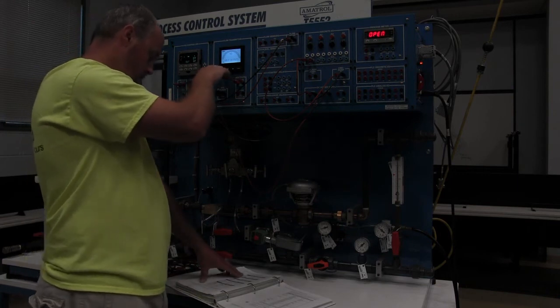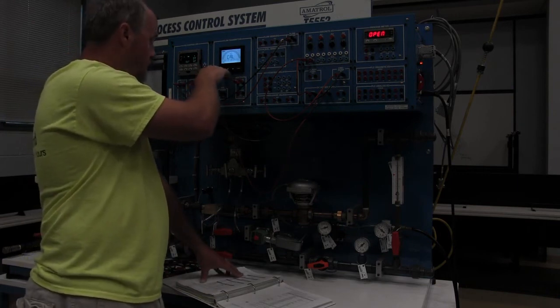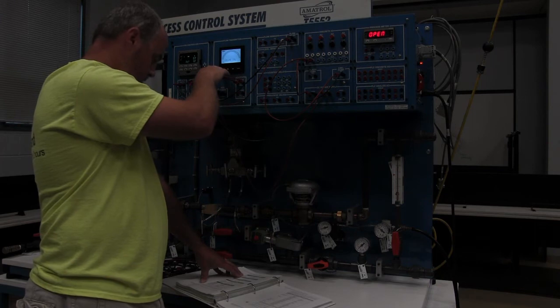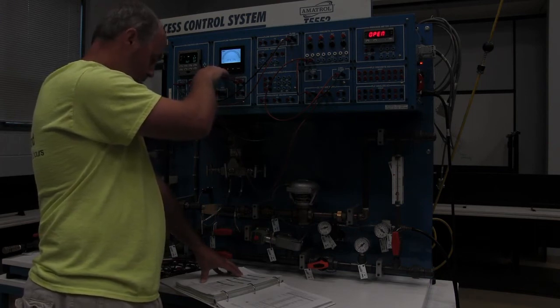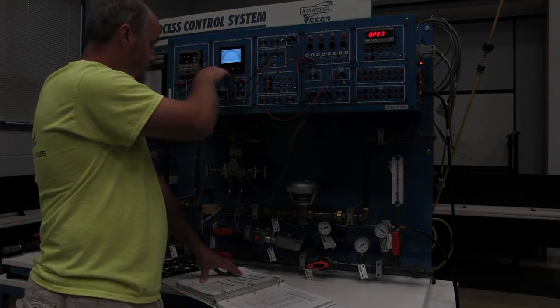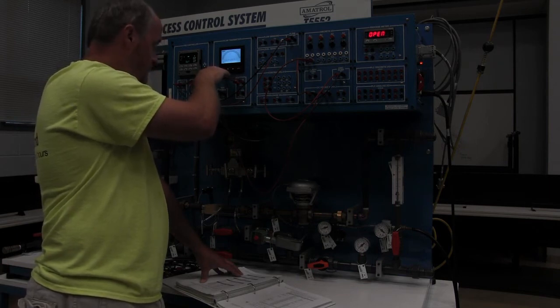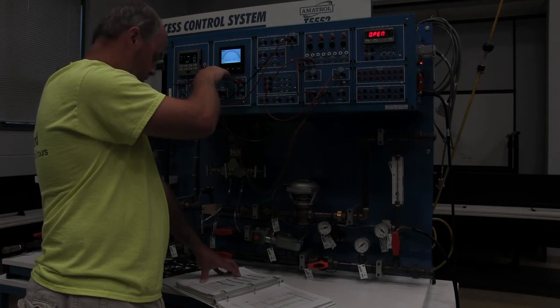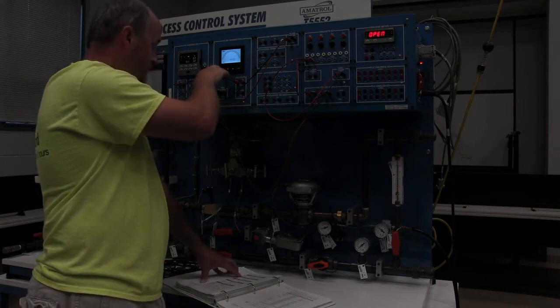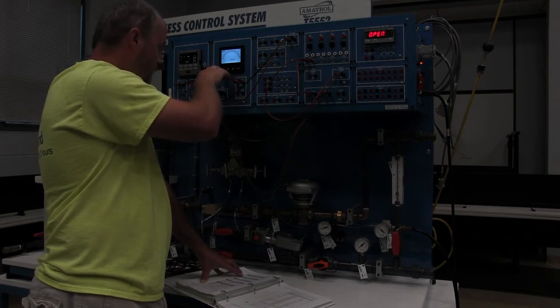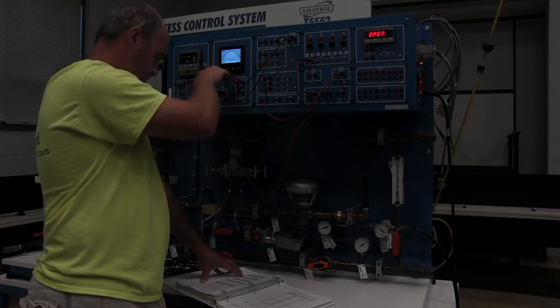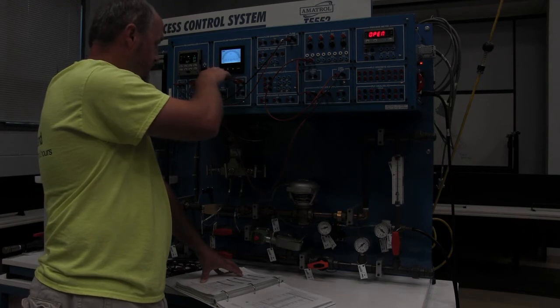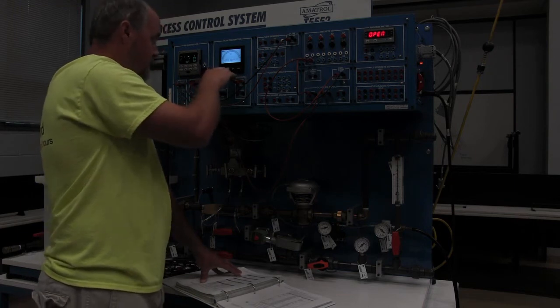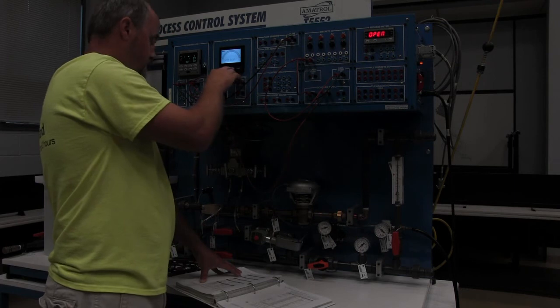So we want no volume cal. Rate cal. Volume cal, we want, it's not applicable. Rate cal is not applicable. TF, we want 1.0, which we have. We want 3160, so we're all good there. So now we're going to go over to our next one.